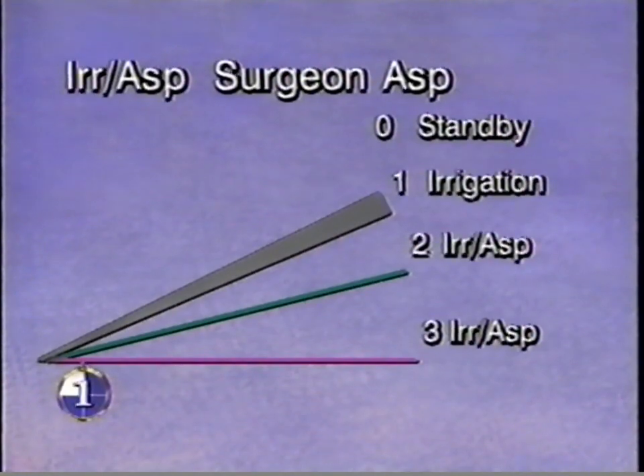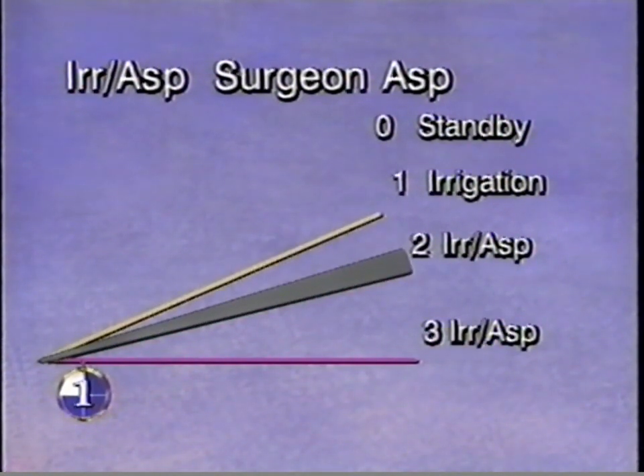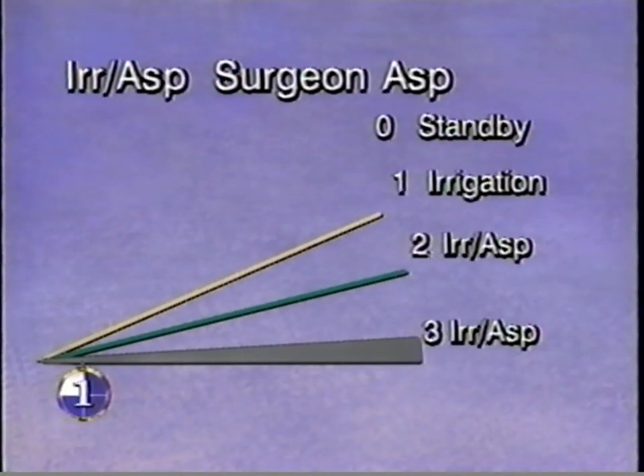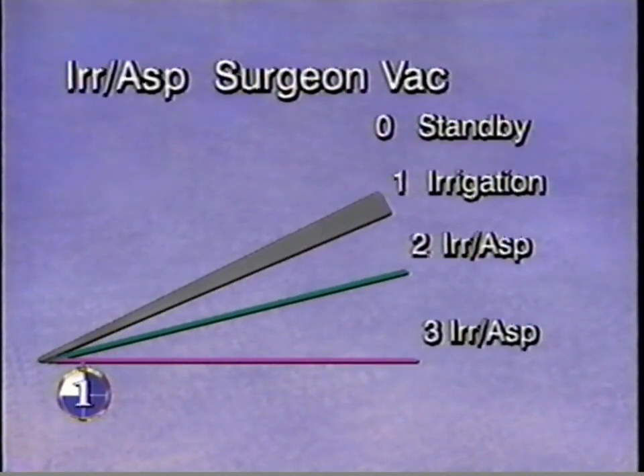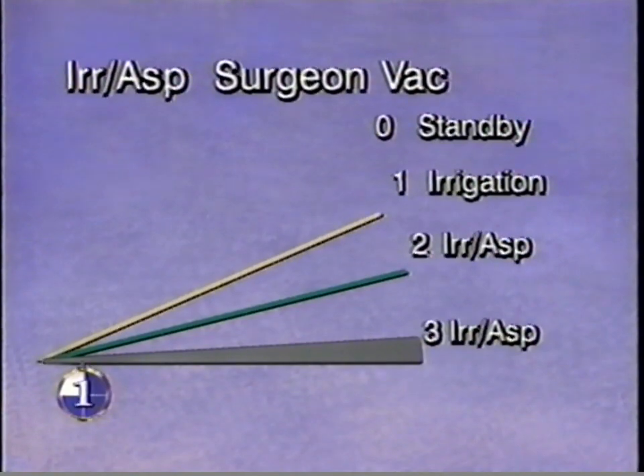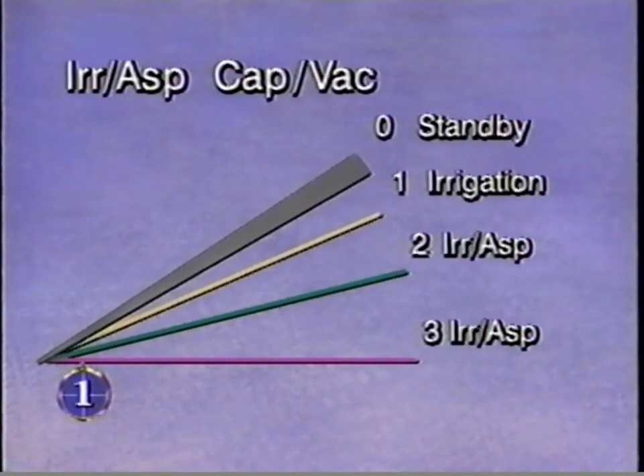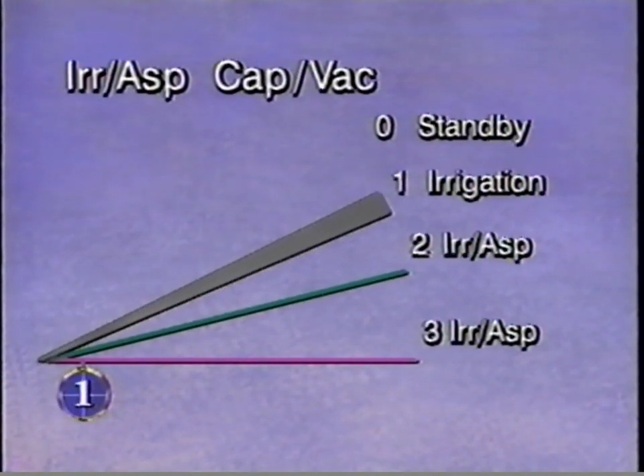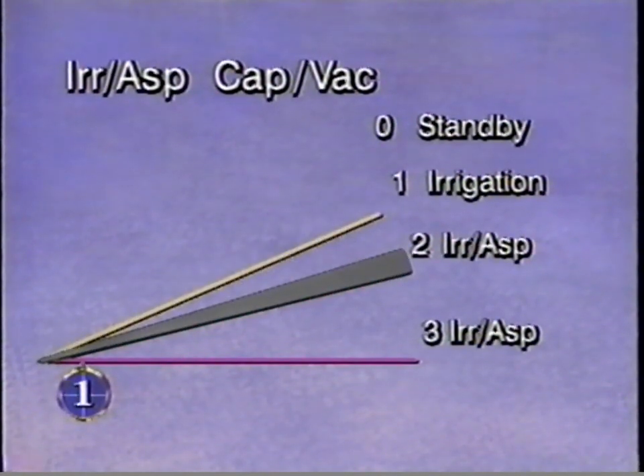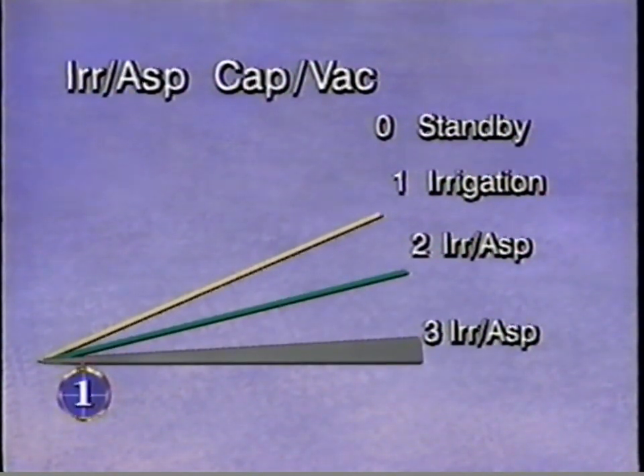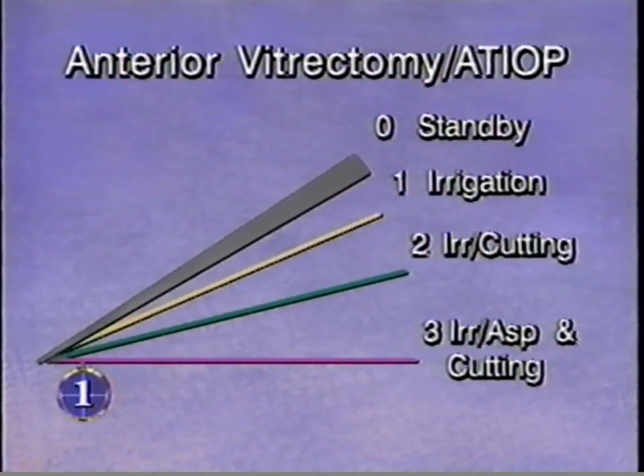When surgeon asp control is used, the IA max and IA min submodes have 2 additional parameters. In the aspiration parameters, positions 2 and 3 allow linear control of aspiration flow rate with fixed vacuum limits. In the surgeon vac parameters, positions 2 and 3 allow linear control of vacuum limits with fixed aspiration flow rate. In the cap vac submode, only panel control is available, providing irrigation in position 1 and irrigation aspiration in positions 2 and 3.